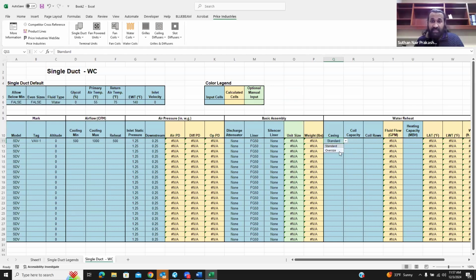The oversized casing is basically to accommodate an oversized coil, which reduces pressure drop by increasing the face area, but you don't have to sacrifice control of the low airflows as well. On the coil capacity, we also have high capacity and standard. Standard is 10 fins per inch. Your high capacity is 12 fins per inch. So I'll pick standard, and I'm going to start with just 2-row coils for now.